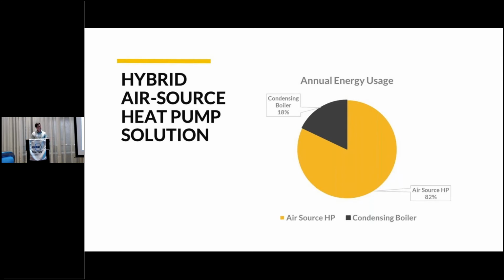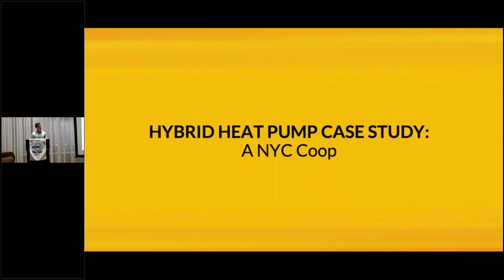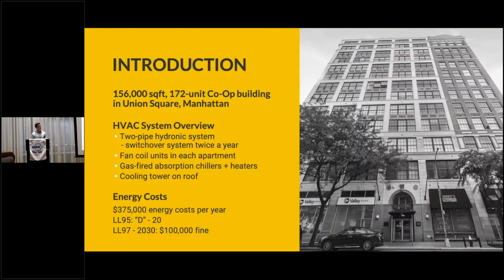So now to put it in action, I'll go through this case study that we worked on. We have a really beautiful co-op building in Union Square. It's about 156,000 square feet with 172 units with some commercial space in the basement. They already had a 2-pipe hydronic system that was connected to a gas-fired absorption chiller in the basement that could be run in heating mode in the winter to bypass the absorption part. But it was a big headache for the maintenance staff. They had to switch over their system twice a year.